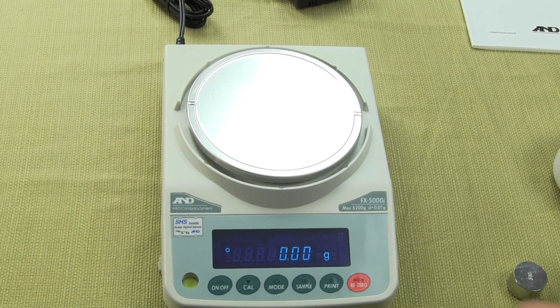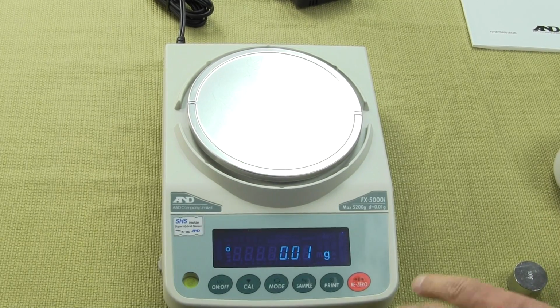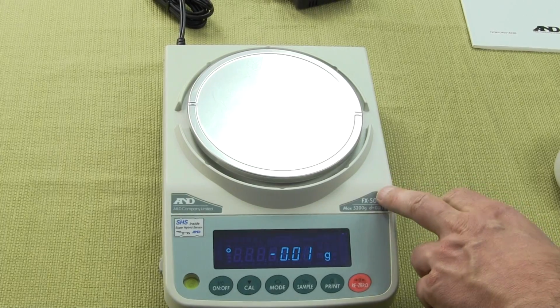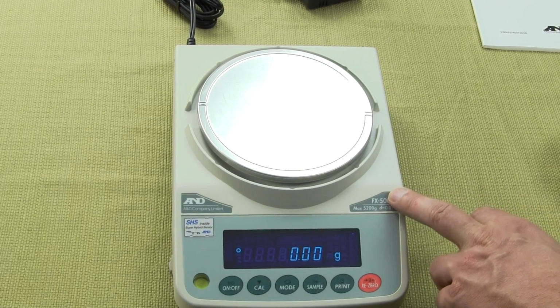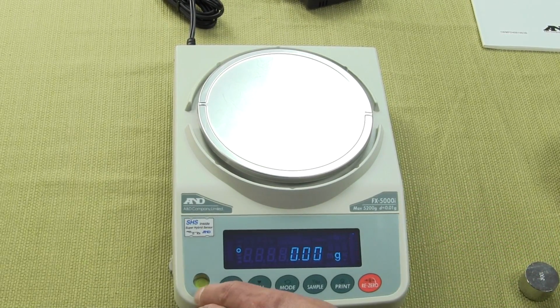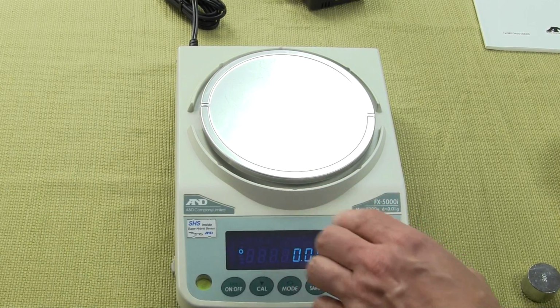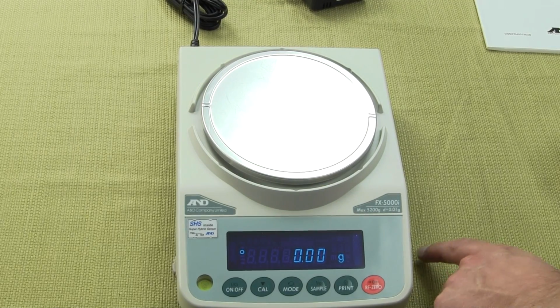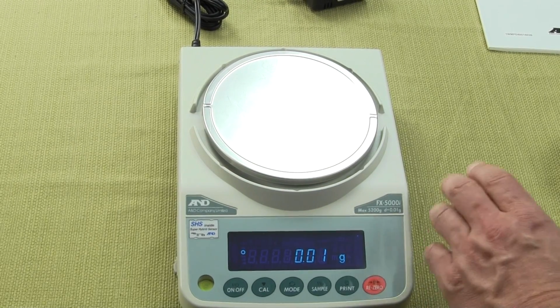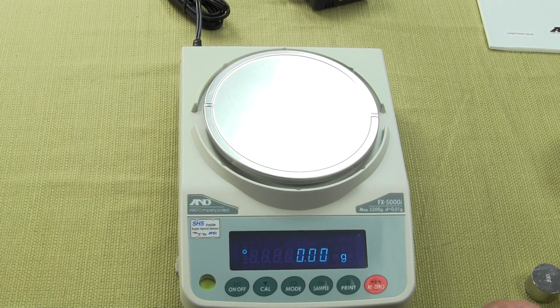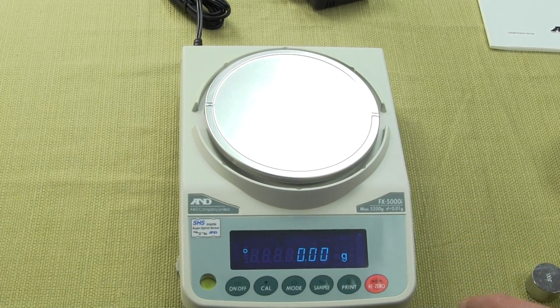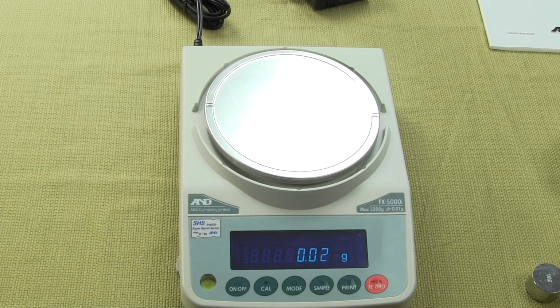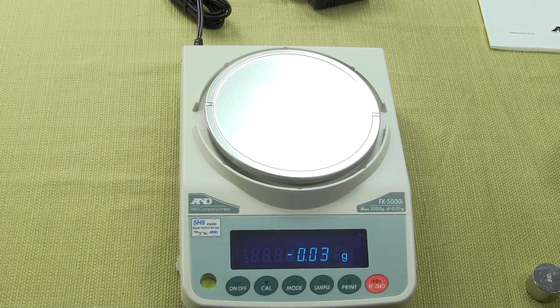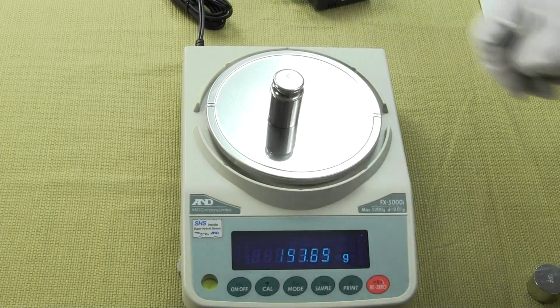We have a 5-year limited manufacturer's warranty. The FZ-i series, very similar to this, does have motorized internal calibration. The balance comes with a spirit bubble indicator in the lower left-hand corner, so that you can level your balance - you have adjustable feet on the bottom. It's critical to always have your balance level. You do have an underhook - I'll flip this balance over in a minute and show you that. This balance is built with a super hybrid sensor, so it's extremely fast.